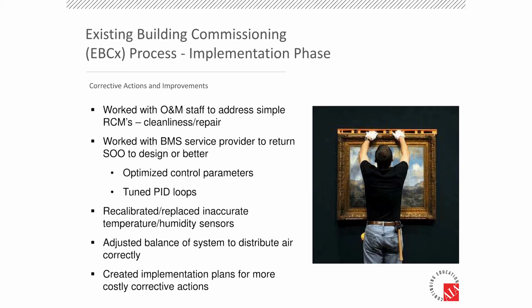Again, it wasn't with a focus on energy savings or anything like that. It was just basic — you guys should really probably fix this kind of stuff. We worked with the BMS service provider to get that air handling unit and those VAV boxes back to where they needed to be. They were really operating in places where they weren't designed to operate. So if you want the best operation out of your equipment, you should really follow that sequence of operation as much as possible.